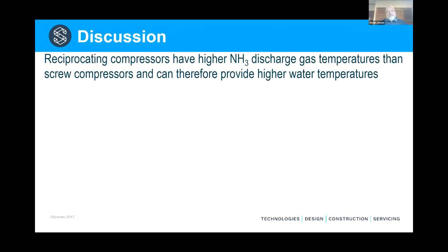And just some concluding remarks about reciprocating compressors versus screw compressors. We see discharge gas temperatures in reciprocating compressors from about 80 to 130 degrees, sometimes up to 150 degrees at part load. With screw compressors, it's much less. Oil injected screw compressors, we see maybe 65 to 85 because a lot of the heat of compression is removed by the oil that's injected between the rotors. We can still recover that heat, but it is at a lower temperature. Typically, the oil temperature in a screw compressor is about maybe 50, 55 degrees entering the compressor and 70 degrees or so entering the oil cooler.